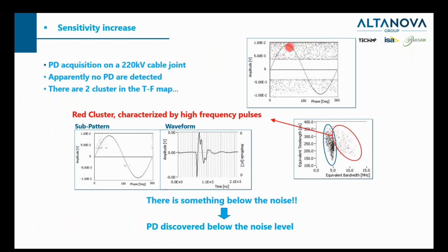Even though the noise is very high in some applications, as we mentioned at the beginning, a big challenge of PD testing is to remove the noise. There is huge noise around here, and we cannot see any discharge signals without proper filtering. So with the TF map analysis, we can split the signals into two parts and only focus on the groups presenting the PD signals. So this is the third advantage, that we can use the TF map as a filtering technology to improve the testing sensitivity. So we can discover the PD signals below the noise level.